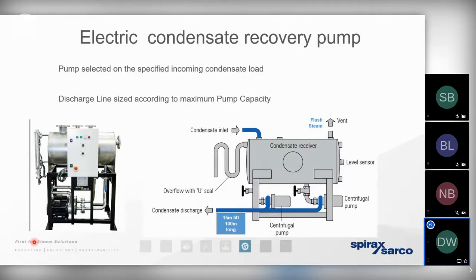It'd simply mean that that condensate could now no longer cool down in enough time. The pumps would be at risk of cavitating and they could back up and that condensate would be dumped to waste. Maybe we've got a failed steam trap. If we've got one or more failed steam traps, we will be bringing plant steam into the condensate receiver.